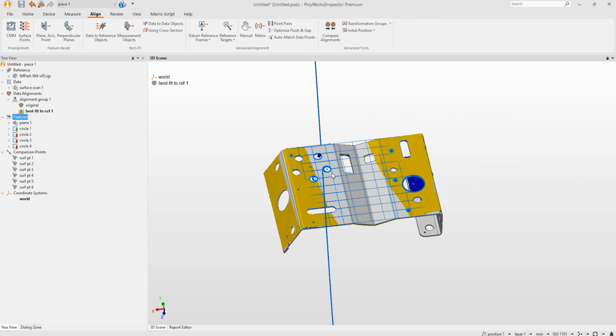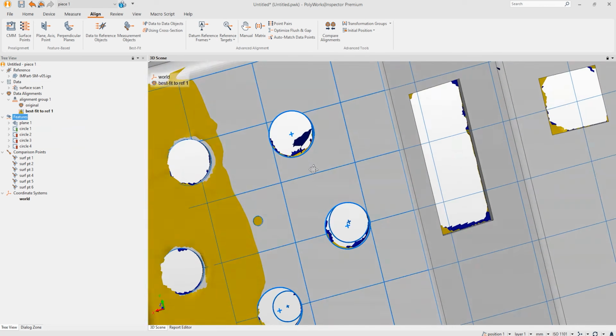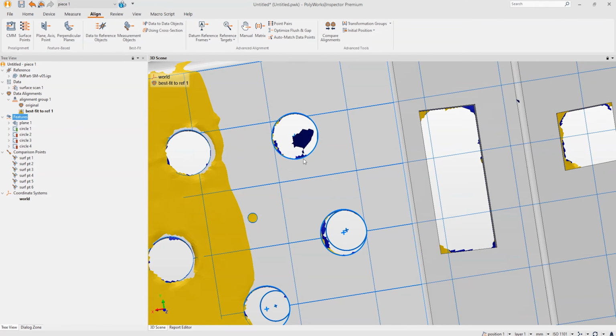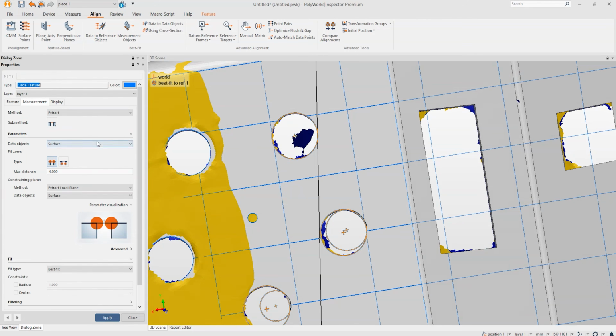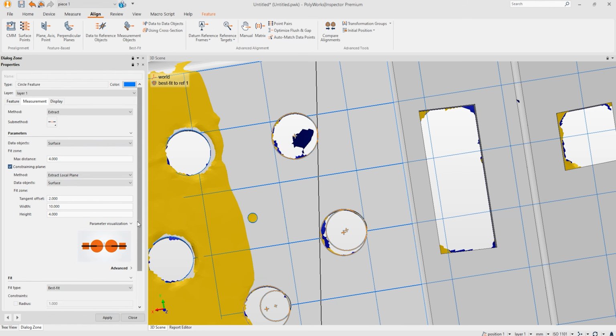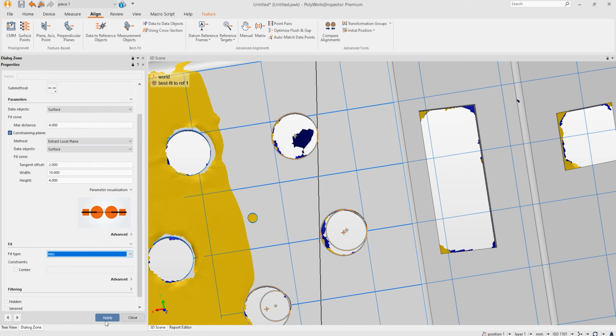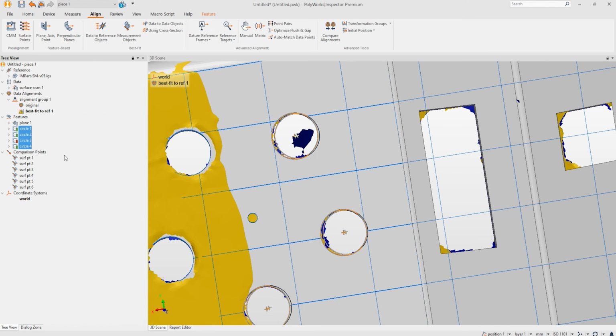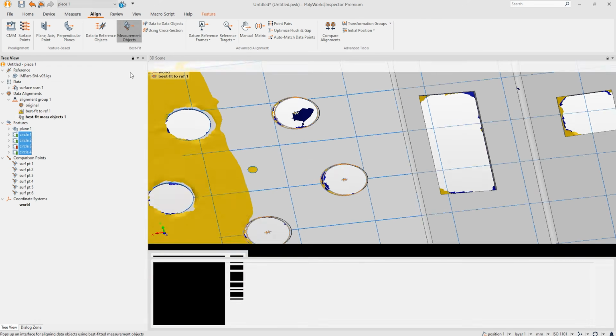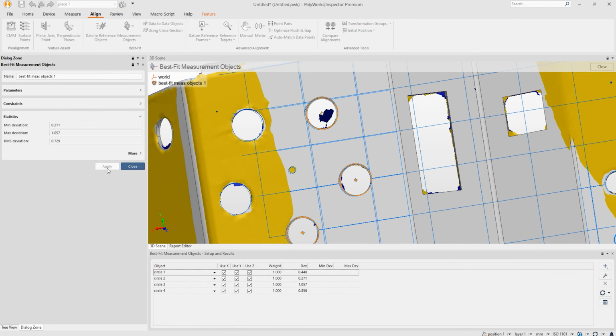Again, similar scenario to previous, one of our circles isn't extracting very well. There's a bit of extra noise in there, but not a problem. We can always go into the properties of our holes. Again, adjust the extraction parameters to make sure they do a better job of extracting, using potentially a trimmed method and using a min fit. And then obviously with that, we can then perform an alignment. In this case, let's change it up. Let's do a best fit measurement object where we're aligning to the centers of the holes. So with those holes highlighted, I can select those and align.